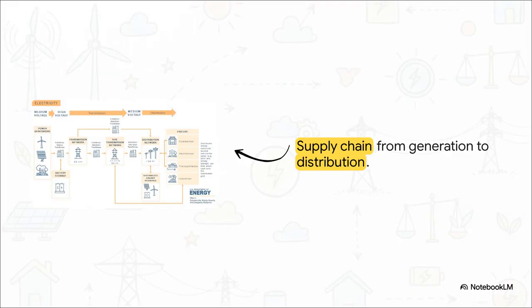To really grasp the future of the grid, we have to ground ourselves in how it works right now. The supply chain basically has three legs: generation, transmission, and distribution. Power surges out from massive plants across high-voltage lines. We're talking up to 765 kilovolts here. These lines use aluminum for conductivity and steel for shear strength. From there, step-down transformers at substations drop the voltage for local distribution.